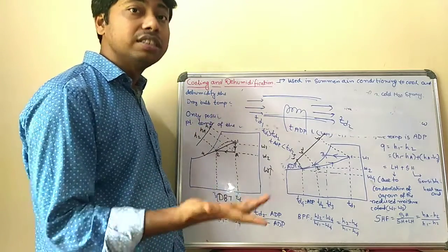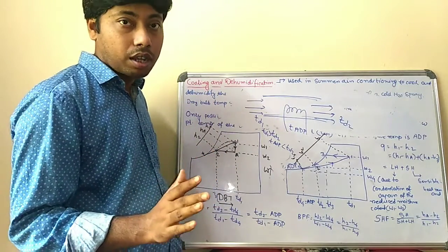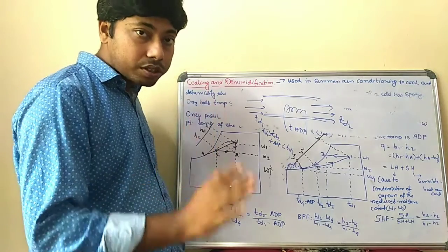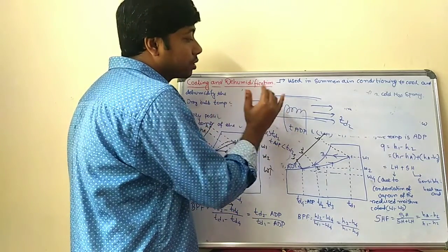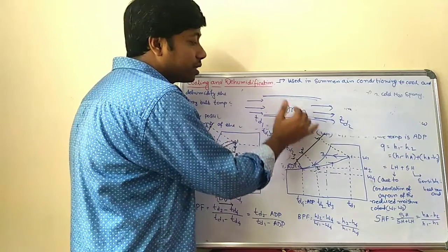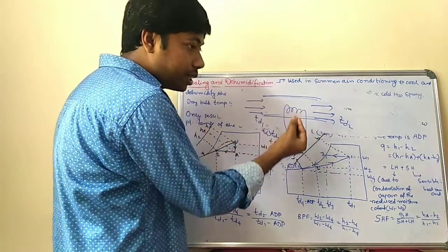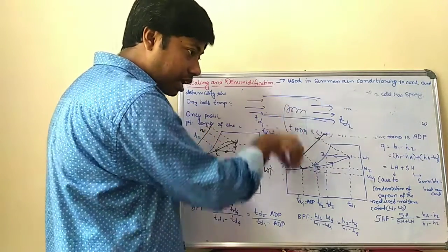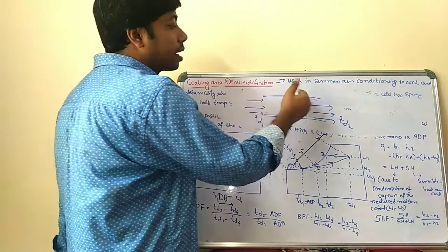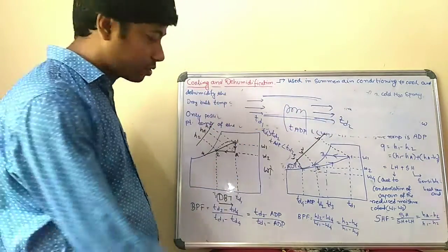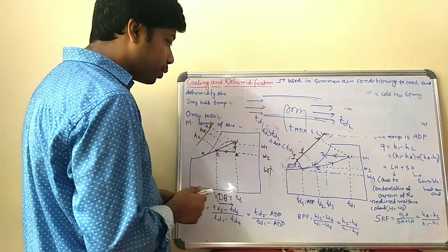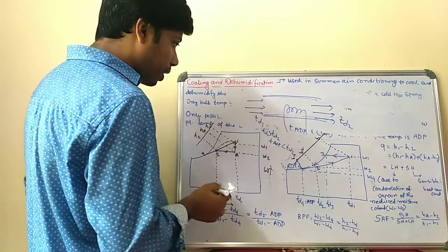If it is not, then dehumidification is not possible, because dehumidification is only possible when condensation takes place. When the entering air contacts this apparatus dew point temperature, some liquid condenses and drops out, and the air passing through is dehumidified as well as cooled. So in this process, the cooling and dehumidification takes place.